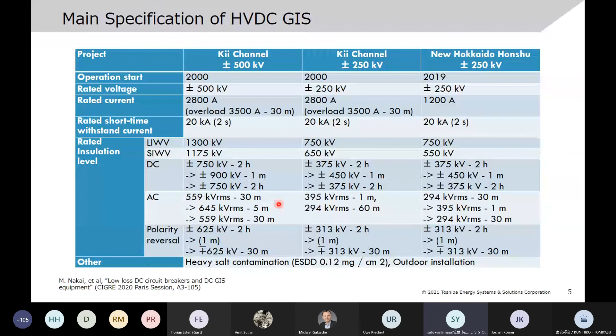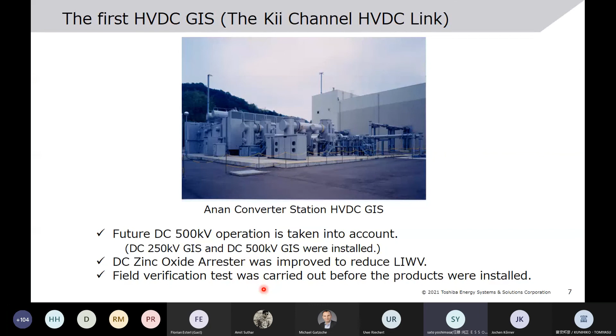From this page, I would like to introduce the outline of the first HVDC GIS development. The picture shows the first HVDC GIS installed at the Anan converter station of the Kii Channel HVDC link. For this link, future DC 500 kV operation is taken into account, so DC 250 kV GIS and DC 500 kV GIS were installed. It is now being operated at 250 kV DC. In order to make the facility compact, the DC zinc oxide arrestor was improved to reduce the lightning impulse withstand voltage (LIWV). Also, a field verification test was carried out for around 1 year before the products were installed, since it was the first experience of HVDC GIS for Japan.